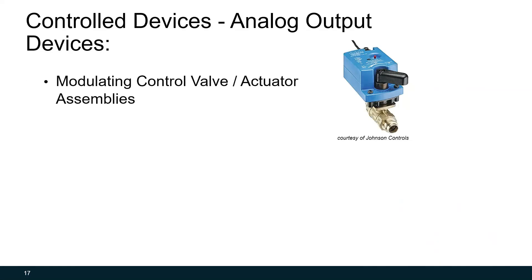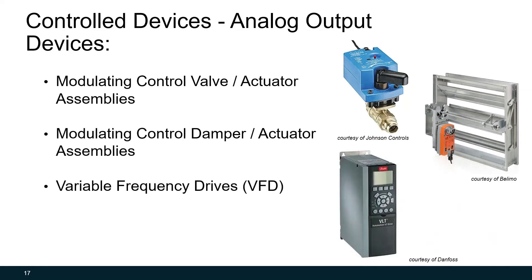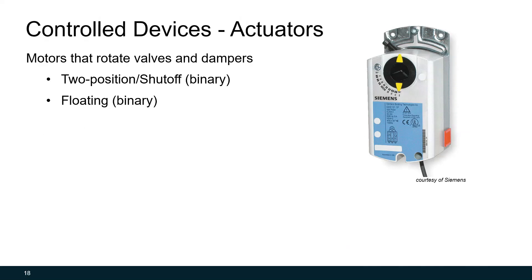There's three main types of analog control devices that you commonly see in HVAC systems. There's the modulating control valve and actuator, the modulating control damper and actuator, and variable frequency drives. We'll go through each of these, but you'll notice that with valves and dampers, they each have actuator assemblies. So what is the actuator? The actuator is simply a small motor that will rotate the valve and damper stems. They can be two-position, as discussed before, so they're binary. They can be floating, which is a version of binary. Or they can be modulating, which is very common as well. The way modulating works is a signal comes from the controller. That signal essentially will be telling the motor, hey, open to 40% open. And the motor will rotate exactly to 40%.